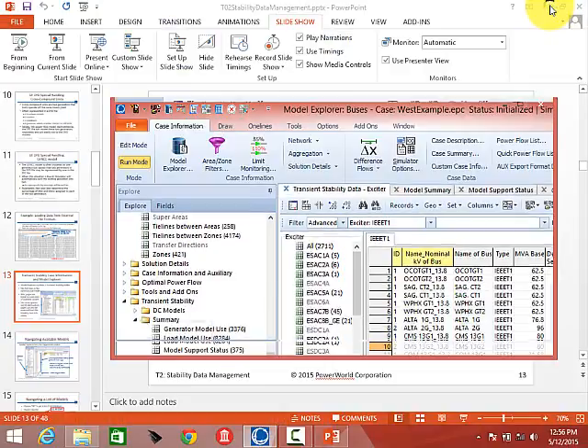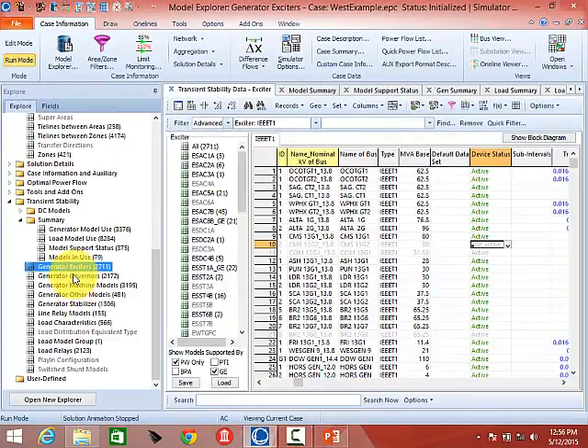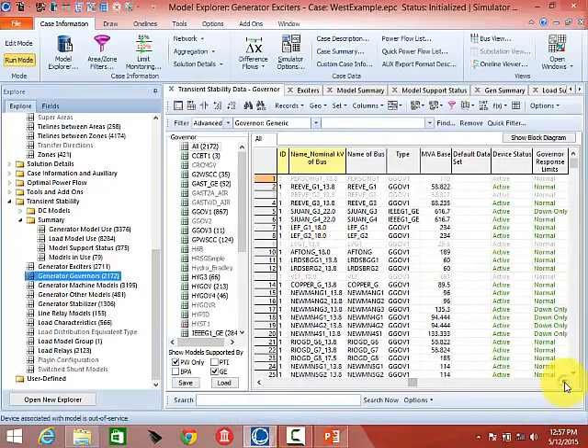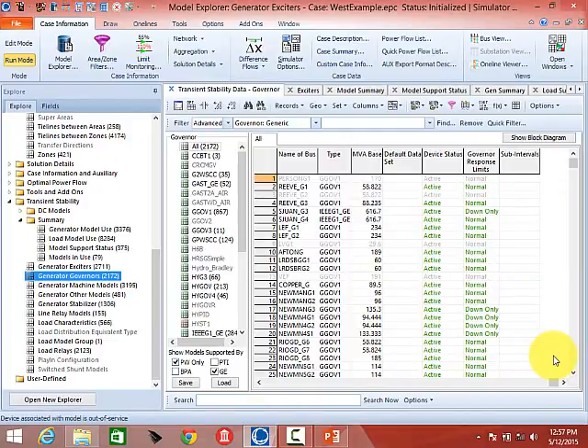There are some special flags accessible here. If you click on Generator Governors, governors have a special flag associated with them — specifically whether the governor can actually respond to a change in frequency. A lot of governors are set so that they do not increase output when frequency is low. If frequency is low you want your governor to push more power out of the machine, but there are many models where they don't increase their power output, and that flag is very important.